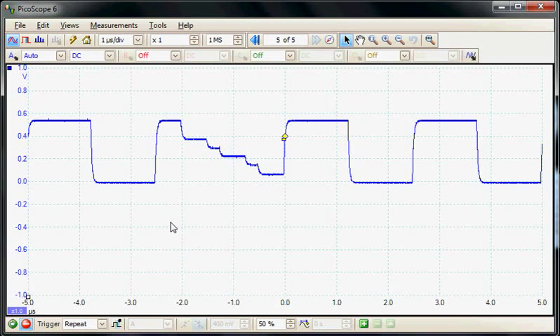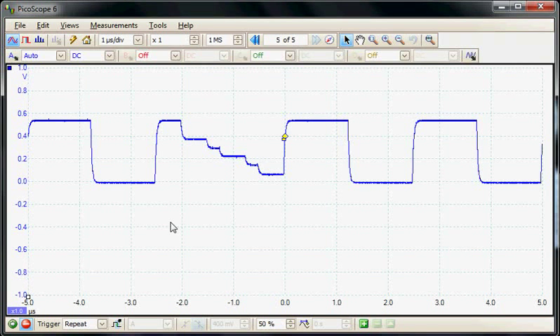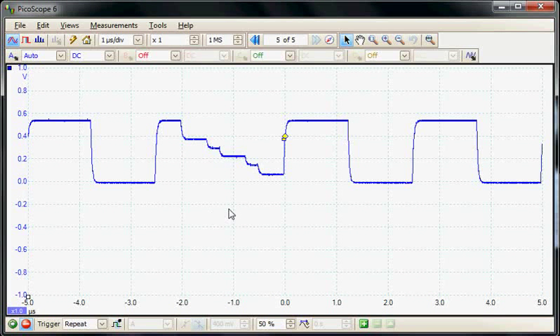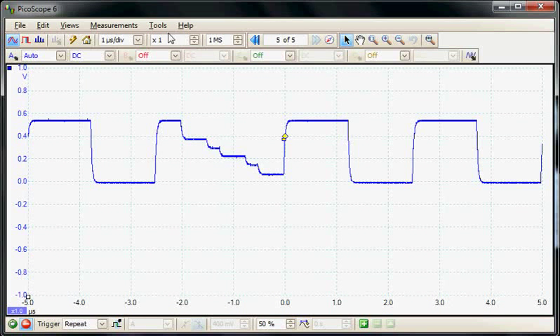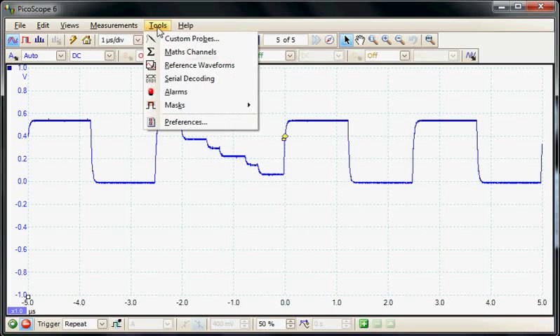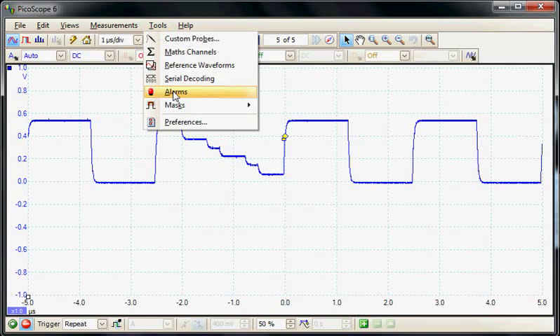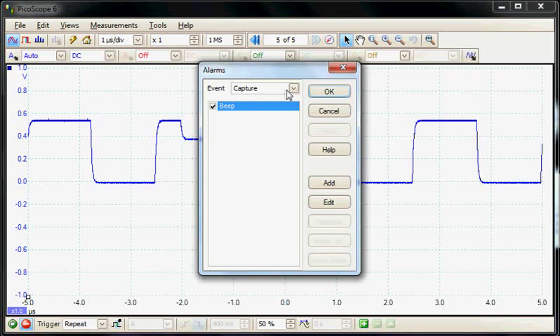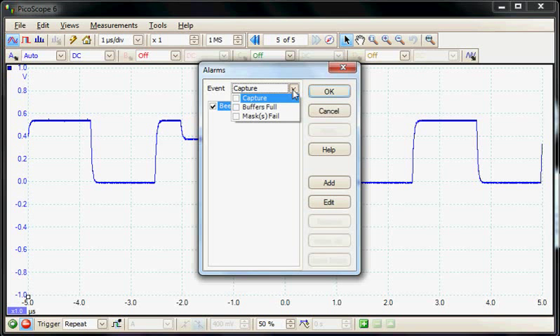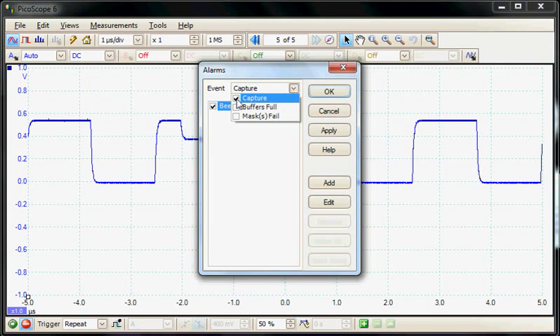The second thing we need to do is define the alarm to save these chosen waveforms to file. This is under the tools menu, selecting alarms, and we want to capture the waveform.